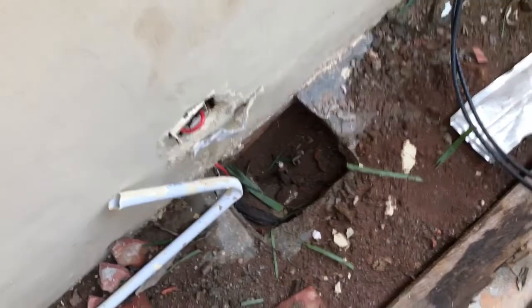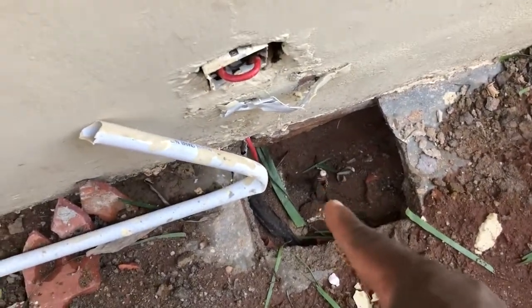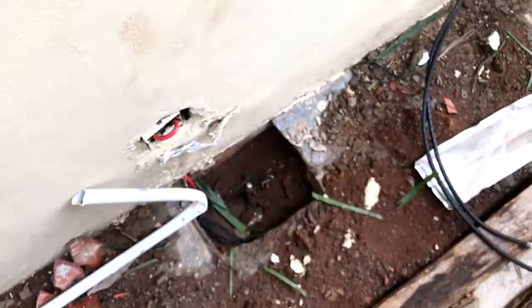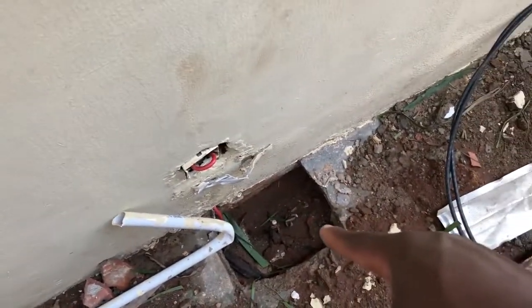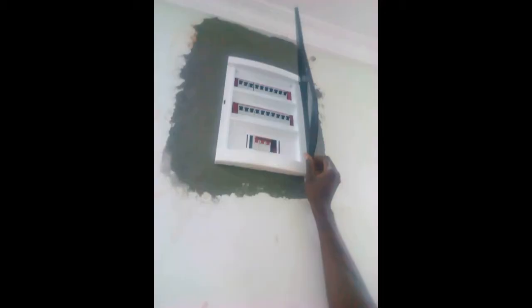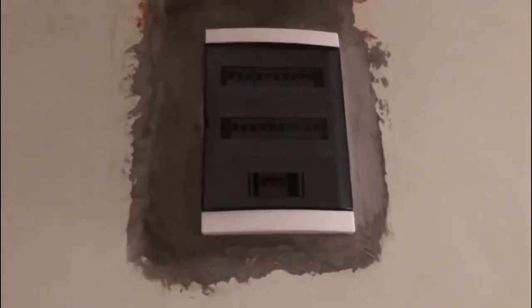On to grounding. We put in another main grounding electrode next to the power room to send a thick 16mm grounding cable to the power room. We've also connected it to the main house. The main distribution board of the house has also been changed to a much more modern distribution board. The circuit selection has already been done, and you can see the breakers inside, including the main breaker. It's nice and plumb, and it's a much better piece of equipment than what was there before, and it means that all circuits are fused properly.